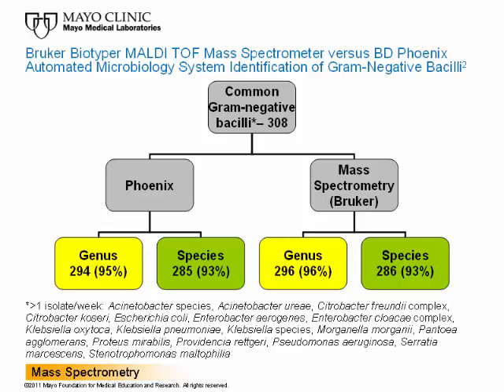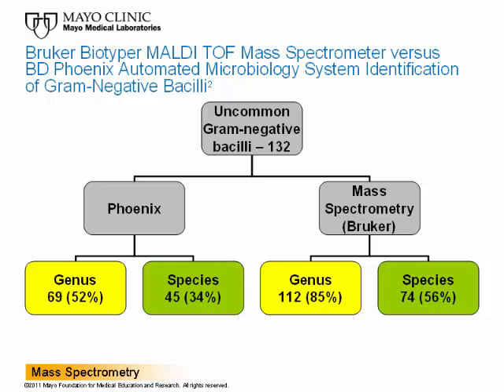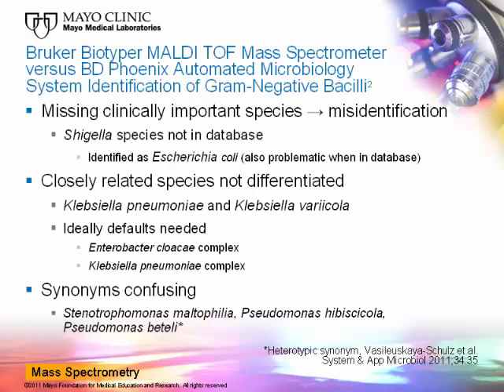The 440 isolates included 308 common gram-negative bacilli — organisms seen more than once a week in our laboratory, including Escherichia coli and Pseudomonas aeruginosa. Both systems identified 93% of common isolates to the species level, and the BD-Phoenix and mass spectrometry systems identified 95% and 96% respectively to the genus level, with no statistical difference between the systems for common organisms. The 440 isolates also included 132 uncommon gram-negative bacilli, where mass spectrometry identified 85% to genus and 56% to species, versus 52% and 34% for BD-Phoenix.